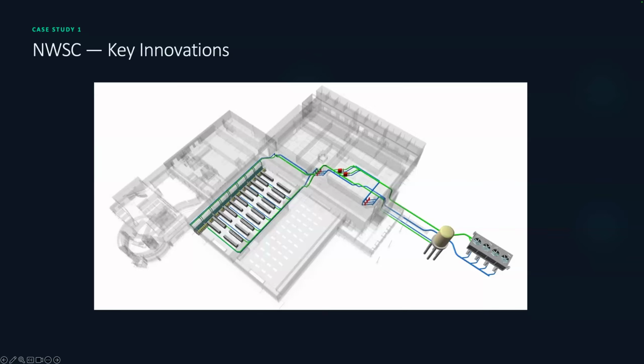the tank will stratify. Hot fluid rises, cold is at the bottom. We draw out of the bottom, and until the hot actually gets down to a level that we can no longer maintain, the thermal storage works against us, but it keeps everything cool for the amount of time that we want to gracefully shut down.